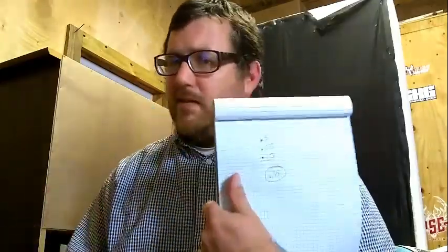But that's basically, when you're designing stuff, especially on a higher level, when I do the commercial load calculations, like I've done a few duct design and load calculations for Great House, and I had to employ some of this stuff because I'll get a design external static pressure for a blower, and I'll have to work back through it. And some of the stuff, you're not going to know exactly what the pressure drop is. You're going to have to use sort of your best guess. You'll look up something similar. You'll look up what you think they're going to use, and you have to design for it.